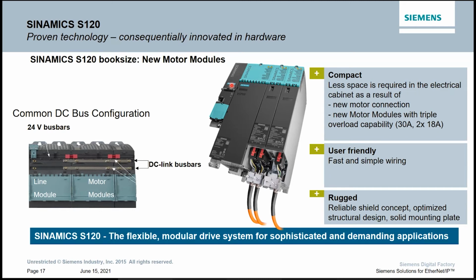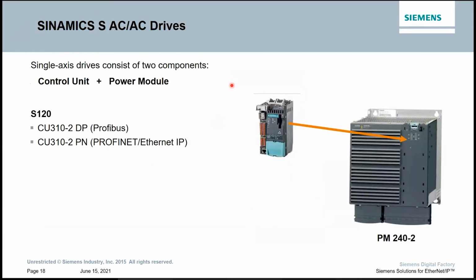For arc flash considerations, Siemens has really taken a hard look at the industry and made their system really flexible. This is the AC to AC version, the PM240. Siemens did this I think about 5 years ago, maybe longer. One power module is utilized for the G series, which is general purpose drives, or the S series, which is our systems drives, higher performance. This power module is the same thing we saw back at the G120s modular system, but if you click on a CU310, now you have a fully functional S120 with the same functionality as the CU320s.